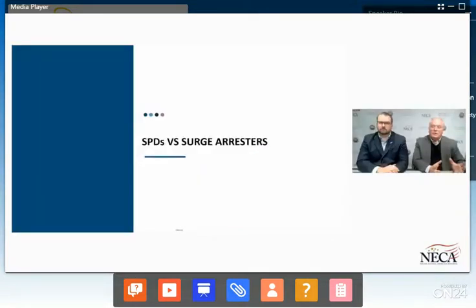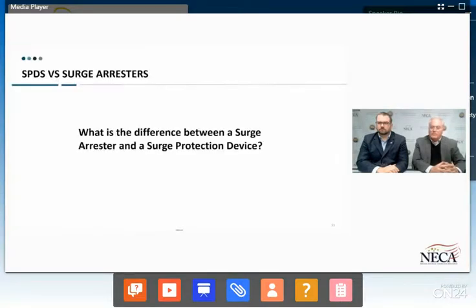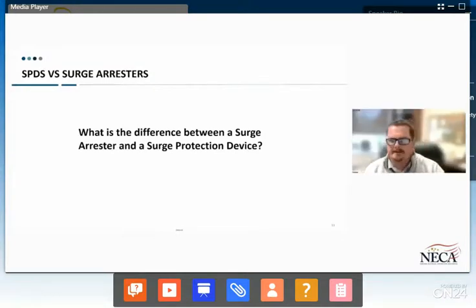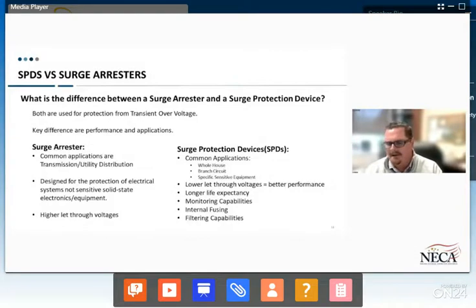We talked about surge protective devices, and we also have another type of equipment referred to as a surge arrestor. Can we help the audience understand and differentiate between the two? Kyle, do you want to weigh in on that? Sure. So surge arrestor versus surge protection device, or SPD - both are used to protect from transient voltages. Really, the key differences are performance and application. With surge arresters, those are typically used in common applications like utility side or protecting electrical distribution systems.